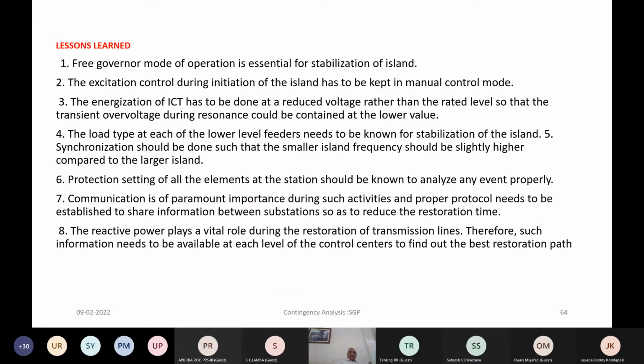These are some of the lessons listed in the paper which was published by the Regional Power Committee. Free governing mode of operation is essential for stabilization of the island. The excitation control during initiation of the island has to be kept in manual control. Energization of the ICT has to be done at a reduced voltage rather than the rated voltage, so that the transient overvoltage during resonance could be contained at a lower value. The load type at each of the lower level feeders needs to be known for stabilization. So when you resume the load step by step, you should be aware of the nature of the load.